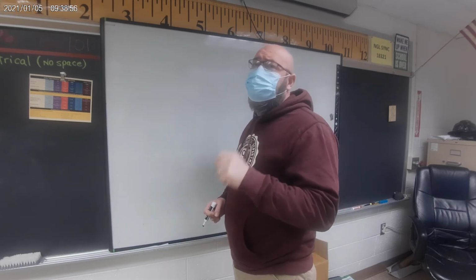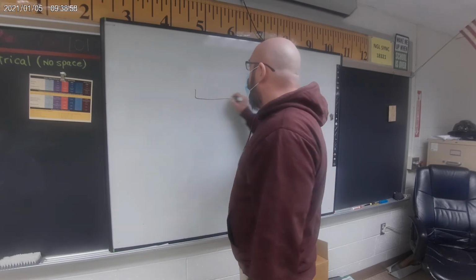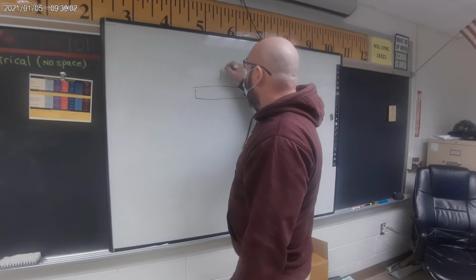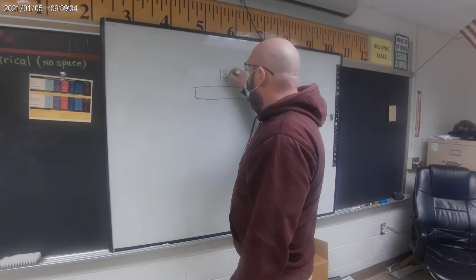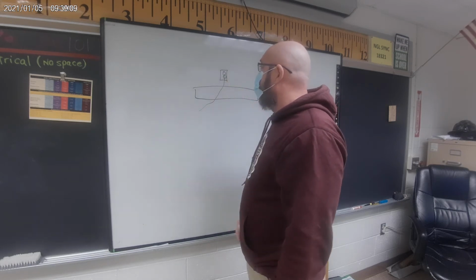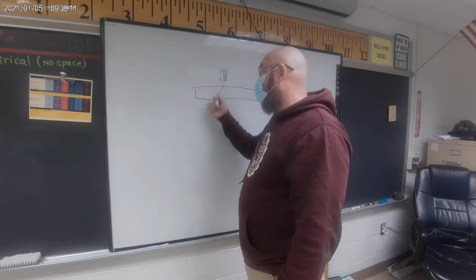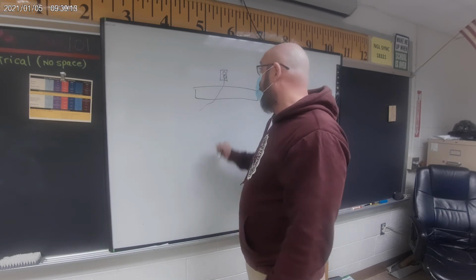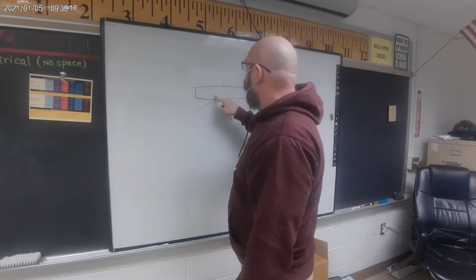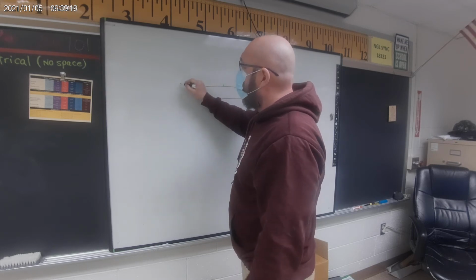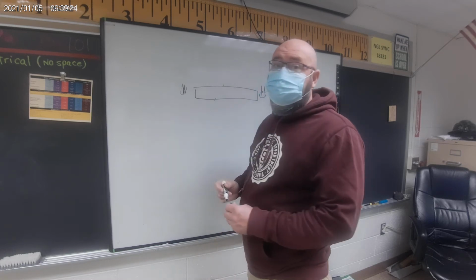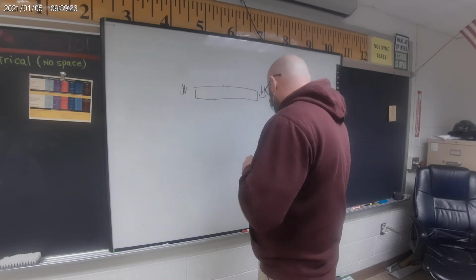And this is important. I can't have any outlets over my baseboard heat, because the cord lays on the heater. That will melt the cord. They get very, very hot. So I have to put them off to the sides of the heater. I would put an outlet here, and I put an outlet here. That's legal. They just can't be over the heater.